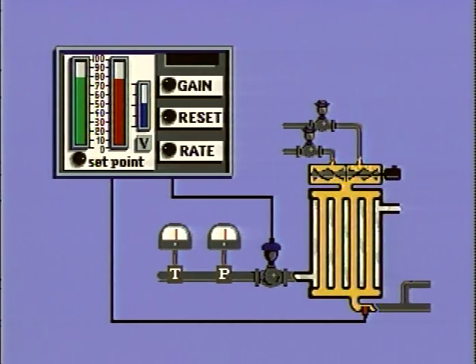Pressure changes occurred when other production lines in the plant increased or decreased their use of steam. When other lines decreased their use, the pressure of the steam supply increased. The temperature of the product began to rise, but it took some time for this temperature increase to travel through the mixture to the temperature sensor. By the time the sensor reflected the rising temperature, the temperature of the product was above the set point.